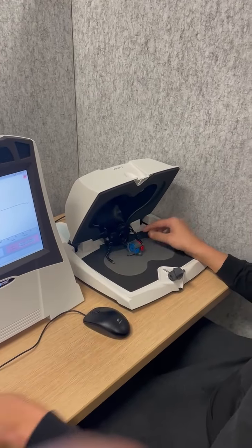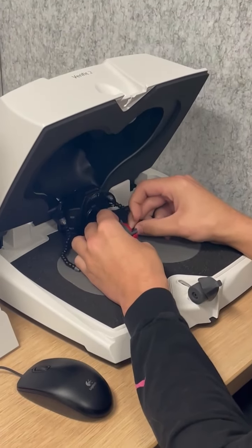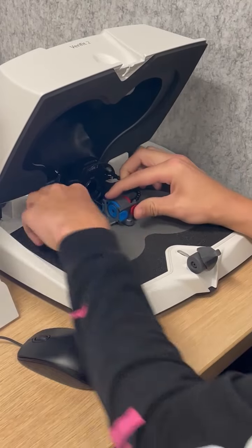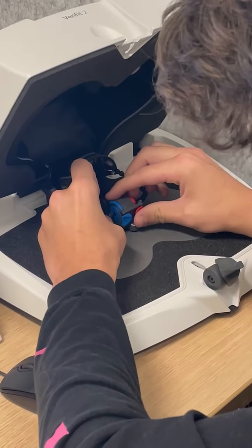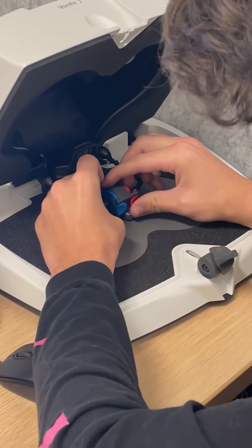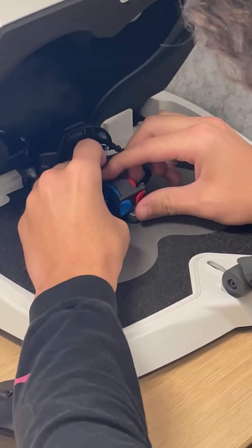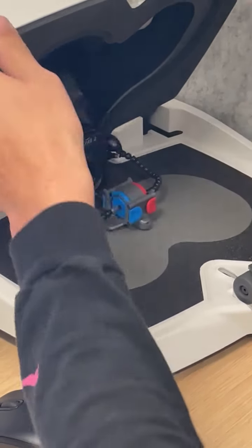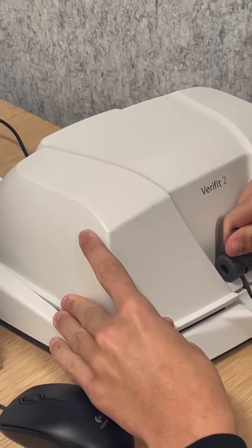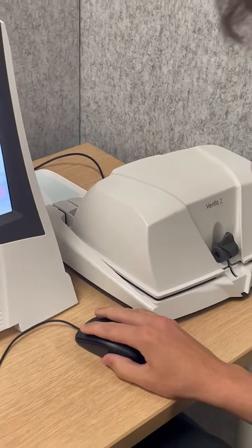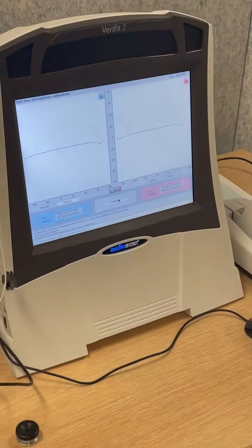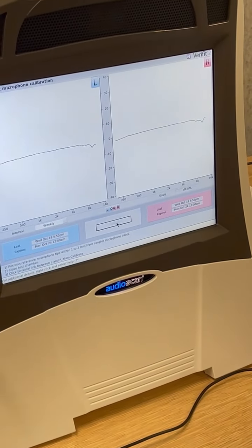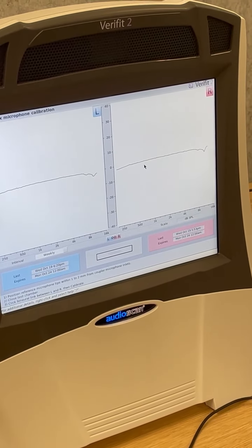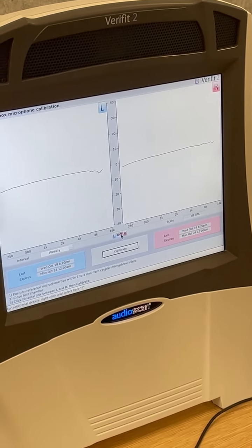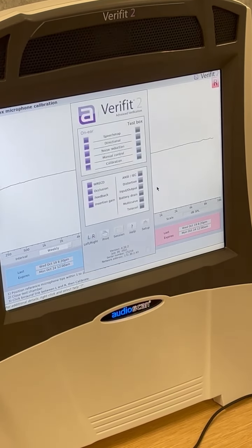So with Verifit 2, you have to calibrate both sides of the coupler mic, and so with that, we want to place both the reference mics within 3 millimeters of the center of each of the sides. So now that we're done placing our reference mics in place, we're going to want to head over to the Verifit, right click and press the test box calibration. And once we're there, we can hit the chain in the middle where it says left and right, and when we press calibrate, it'll calibrate both sides for us.